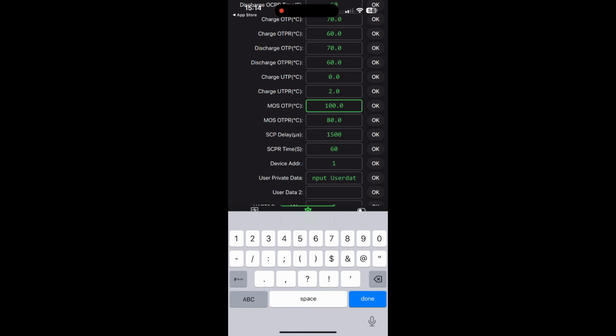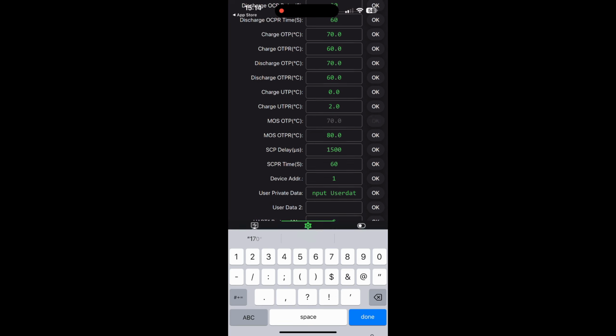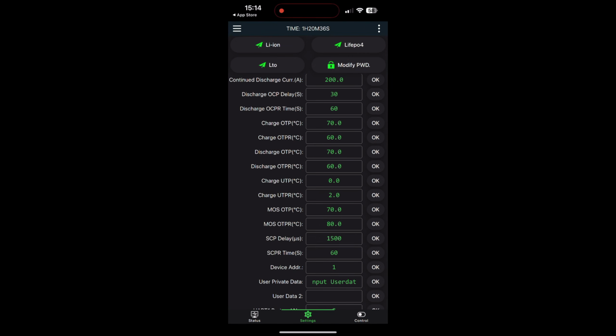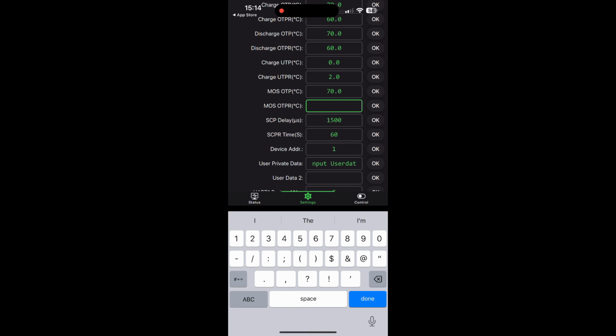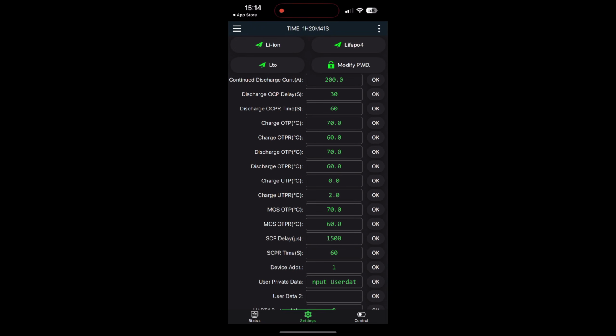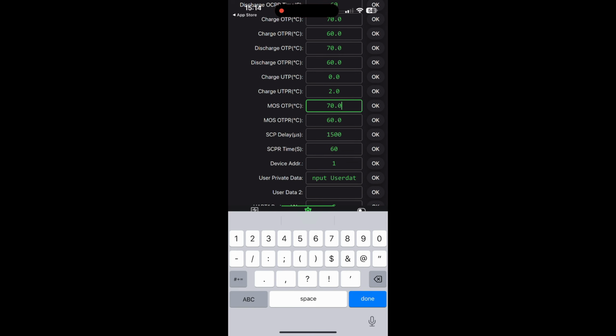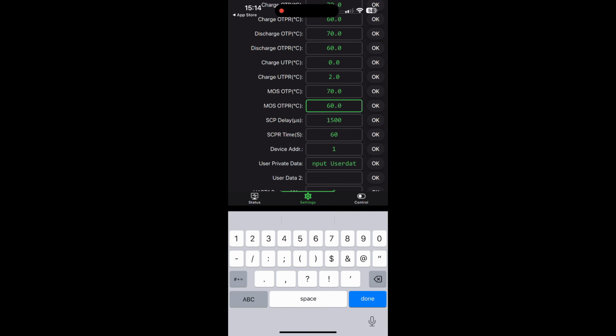MOS over temperature protect. Inside the BMS, they have something called a MOS. If the temperature goes above 100 degrees, which I think is pretty excessive, I personally would change that back down to say 70, and it's going to throw a hissy fit because this one is above it, so we'll change that to 60. So if the MOS temperature within the BMS reaches 70 degrees, again it'll stop. Once the temperature comes down below 60 degrees, it'll allow the BMS to continue working.